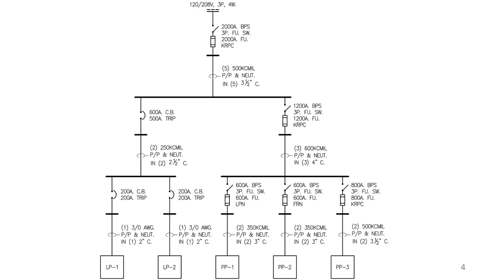Now, of course, when I have these low voltage feeders, these smaller feeders, there's not too much arc flash hazard that can exist there because they're small wires. However, if you're running it very long, it's going to take a long time for this 500 amp device to trip. And this is an issue that I see in a lot of old facilities that haven't thought about this, where the arc flash is never looked at, and you have very long runs, and it takes a very long time for devices to clear a fault. And you end up with a huge explosion, and you can kill somebody. So this is just going through a couple of different things.